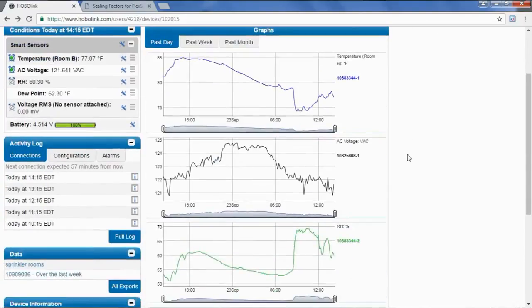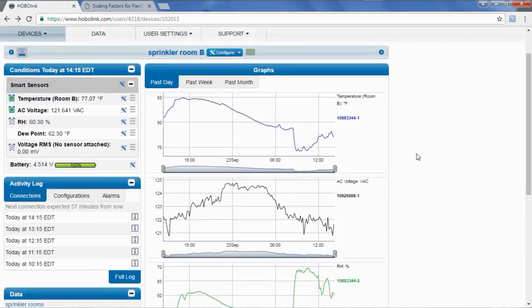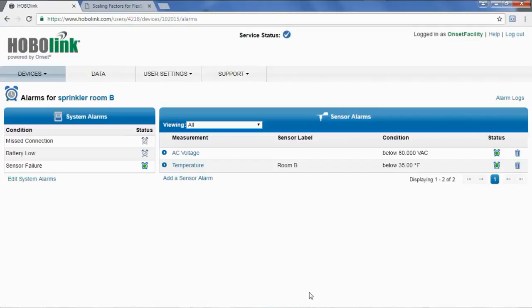What we did is we set up alarms so that our facilities people would be notified if there was a power outage or if the temperature got too cold in this room. The way you set up alarms with HOBOlink is you go up here to configure and click on alarm configuration. And you can see here are my two sensor alarms. If the AC voltage goes below 80 volts AC, we get notified. Also, if temperature goes below 35 degrees, we will get notified of that also.